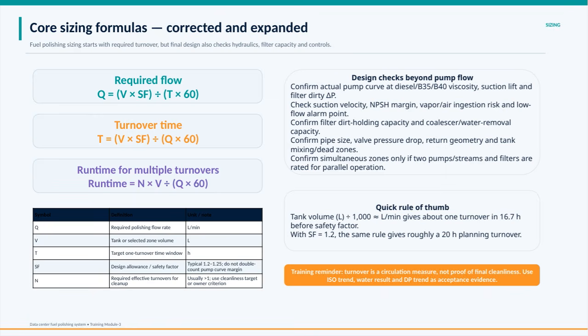Filter capacity is critical too. Both dirt holding and water removal must be confirmed so filters can perform effectively. Also, consider pipe size, valve pressure drop, and how return lines and tank mixing zones might impact flow. If you're dealing with multiple zones and pumps in parallel, make sure the equipment is rated accordingly. A quick rule of thumb is that tank volume divided by 1,000 approximates the flow rate in liters per minute needed for about 1 turnover in 16.7 hours, before adding a safety factor. With a safety factor of 1.2, this gives you around a 20-hour turnover window for planning.